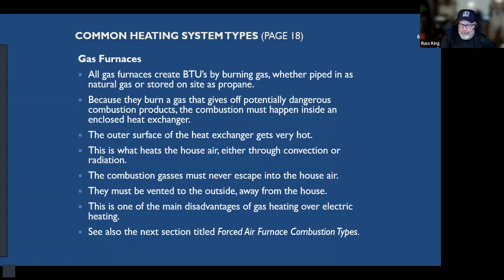Gas furnaces. All gas furnaces create heat by burning gas. Now, when they burn gas, they give off potentially dangerous combustion products. So there's water, there's carbon dioxide, and there's carbon monoxide. And it's the carbon monoxide that's very, very bad for you. All this flame happens inside of a tube, and we call that tube a heat exchanger. You never, ever want the air that's coming into your house to come in contact with those combustion products. You want to keep those separate. So you're burning the gas inside this tube, and all the combustion products go outside the house, but this tube itself gets really, really hot. And so if we can blow air across the outside of that tube, we can heat that air without it coming in contact with the combustion products themselves.